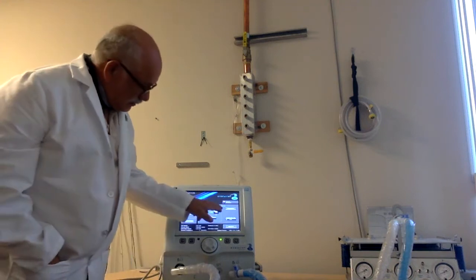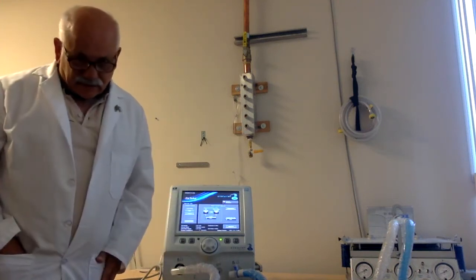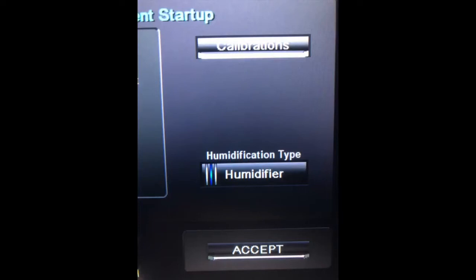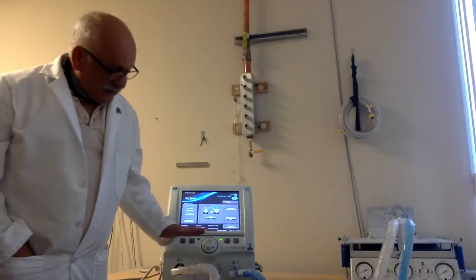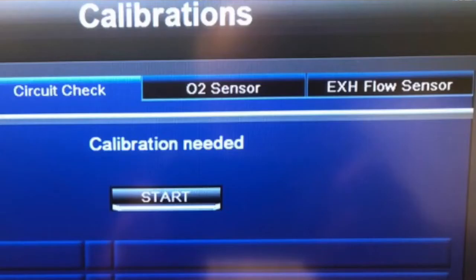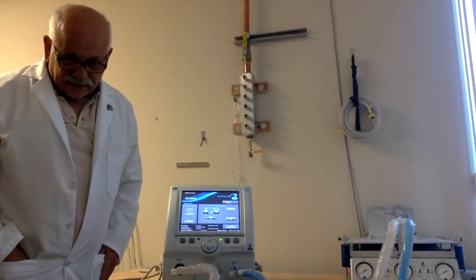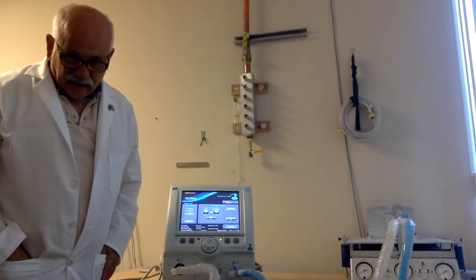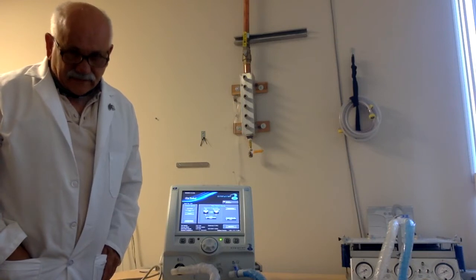at the calibration area. Now for this demonstration, I'm not going to go through the calibrations, but they're simple. You can calibrate the circuit and determine the compliance and resistance of the breathing system. You can calibrate the expiratory flow transducer, and you can calibrate the oxygen sensor. This ventilator, like all ICU ventilators, comes with a built-in oxygen sensor. This one is a galvanic sensor.